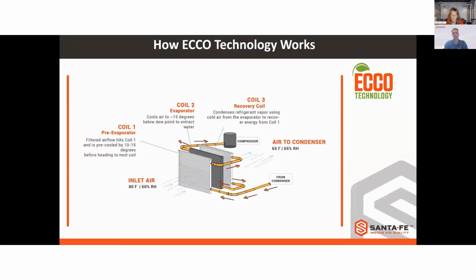So similar to what our heat exchanger core did in our older units. And then when it hits that evaporative coil, it's going to go 15 degrees below dew point to really extract that water. And then it's going to go through that third coil. Now, when it's coming out of these three coils, we've got about a 30% grain depression going from when it's going in to coming out. And that's even before it goes to the condenser. So again, this 3-pack of coils really allows us to remove a lot more water, more energy efficient.